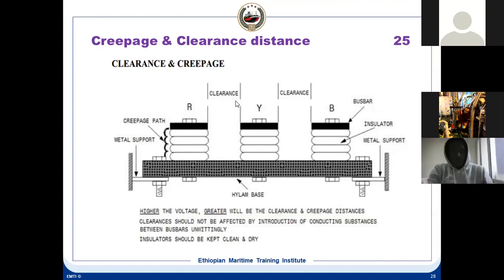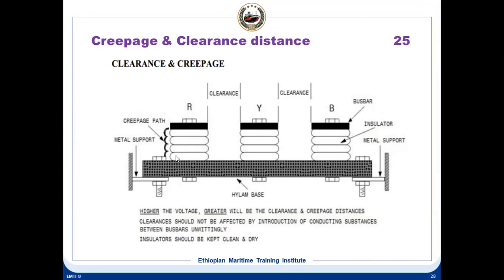And what is creepage? Creepage is the distance over the area of the insulator. With three phases RYB, the distance in air is known as the clearance, and the distance over the insulator is known as the creepage distance. The higher the voltage, the greater the clearance and creepage distance. Clearance should not be affected by the introduction of conducting substances between bus bars unwittingly. Insulator should be kept clean and dry.